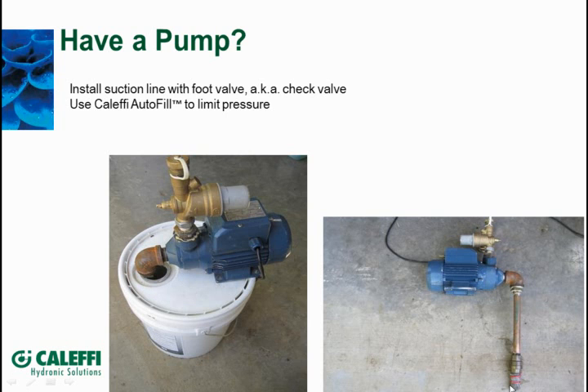It self-primes because as you drop it in there, of course, the fluid pumps right up to the pump. And then I said, now I want you to fill all these systems up to 30 pounds pressure. I said, go beyond that, you could pop the relief valve, and then you're going to blow all this expensive glycol right down the drain or right on the floor.